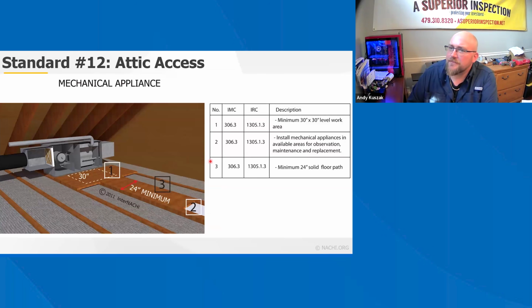Attic access. Mechanical equipment in attic spaces or crawl spaces should be accessible for service and removal. In addition to an adequately sized access opening, a passageway should be provided. In an attic, the passageway should be made of solid flooring.